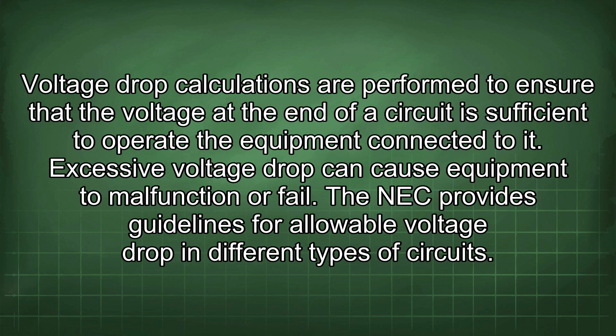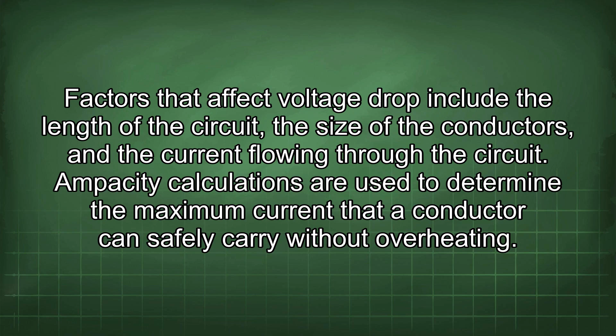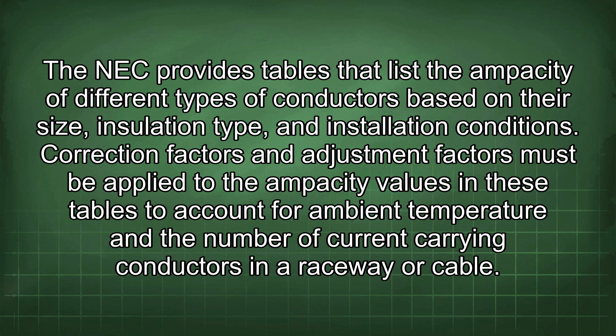Factors that affect voltage drop include the length of the circuit, the size of the conductors, and the current flowing through the circuit. Ampacity calculations are used to determine the maximum current that a conductor can safely carry without overheating. The NEC provides tables that list the ampacity of different types of conductors based on their size, insulation type, and installation conditions. Correction factors and adjustment factors must be applied to the ampacity values in these tables to account for ambient temperature and the number of current carrying conductors in a raceway or cable.